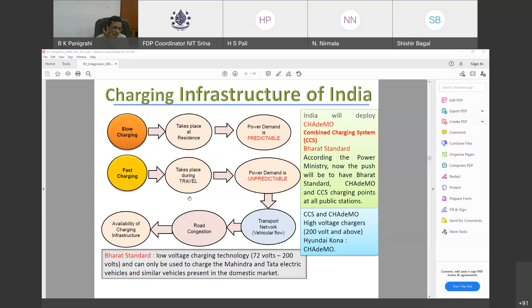So that's why these are the effects of fast charging on the grid, on the low voltage and medium voltage distribution network. Depending on the charging characteristics and the power level, you may have difficulty controlling the high ramp rate or down rate, because suddenly many vehicles are coming to charge. So there is a need to ramp up the current requirement, ramp up the power requirement. Similarly, it may cause power quality issues because this is DC charging. Your DT, the distribution transformer, may be overloaded, the distribution feeder may be overloaded. And particularly this becomes a challenge when you want to implement demand side response and have different values of the tariff.